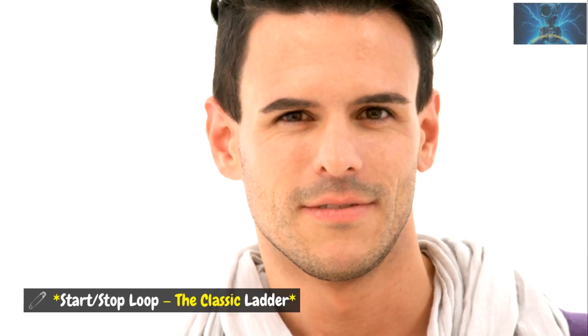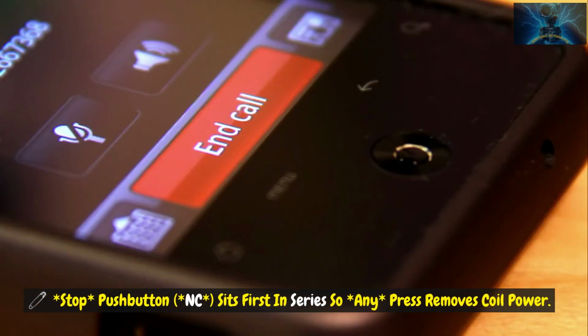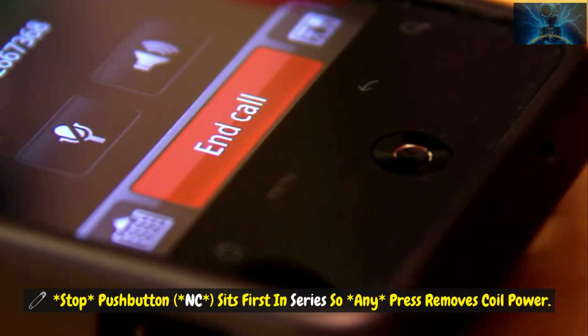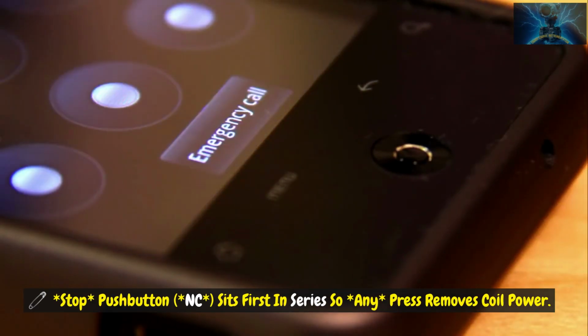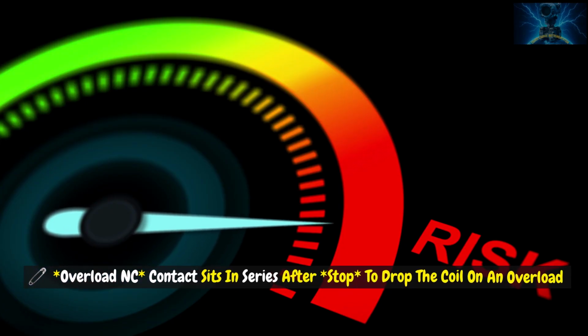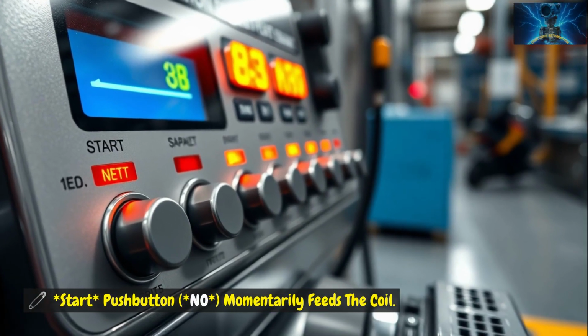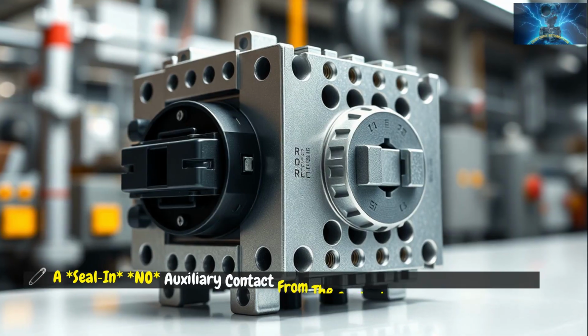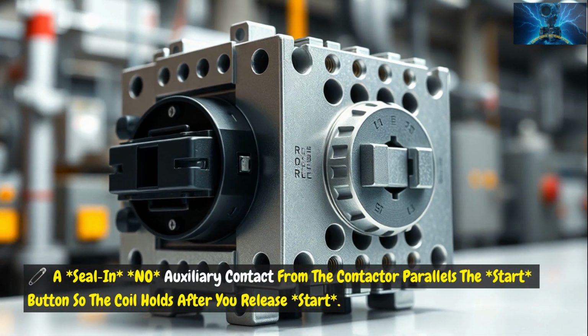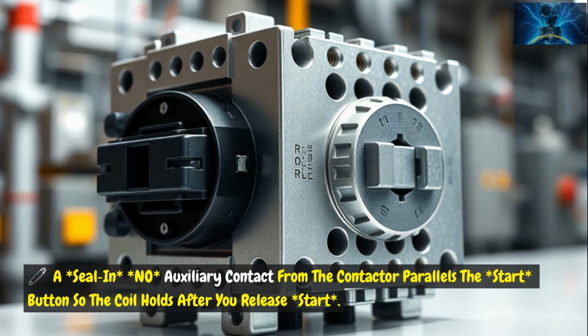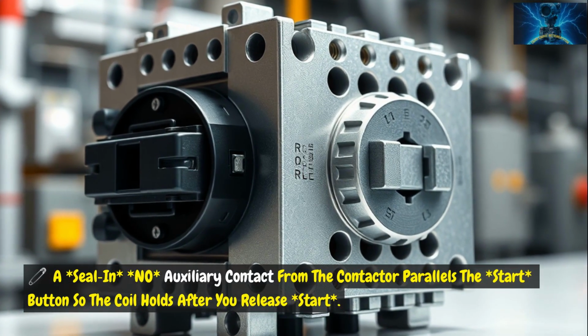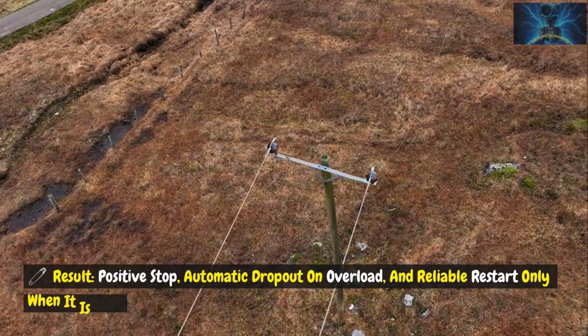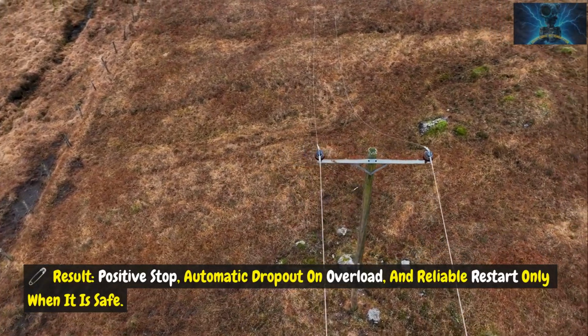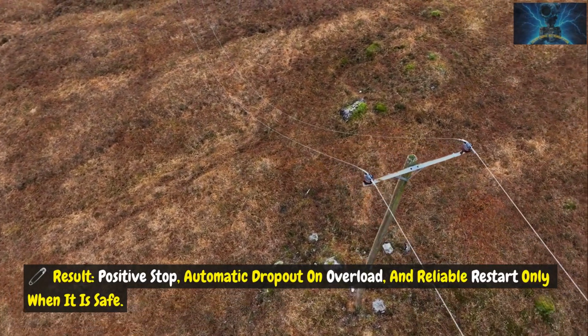Start, stop loop, the classic ladder. Stop push button: NC sits first in series, so any press removes coil power. Overload NC contact sits in series after stop to drop the coil on an overload trip. Start push button: NO, momentarily feeds the coil. A seal-in NO auxiliary contact from the contactor parallels the start button, so the coil holds after you release start. Result: positive stop, automatic dropout on overload, and reliable restart only when it is safe.